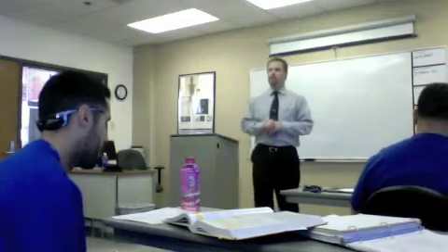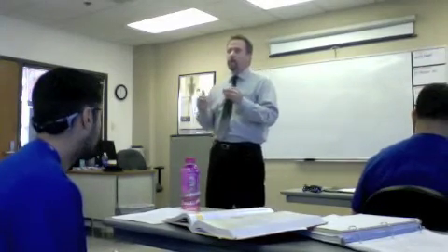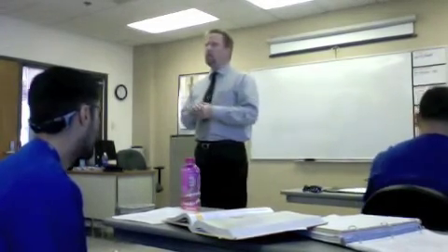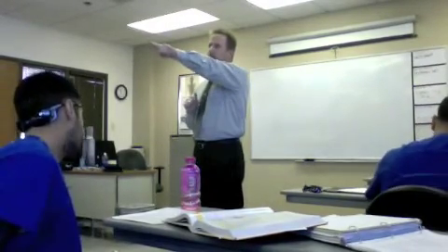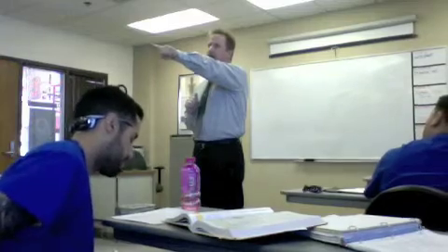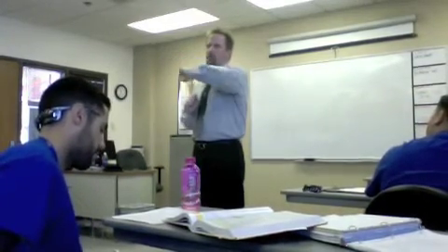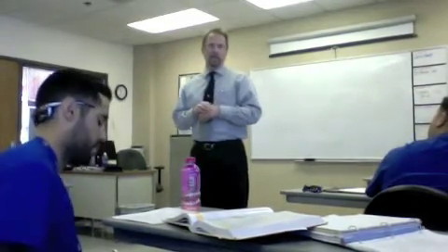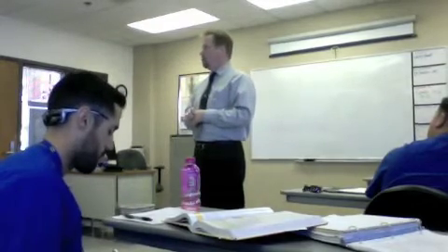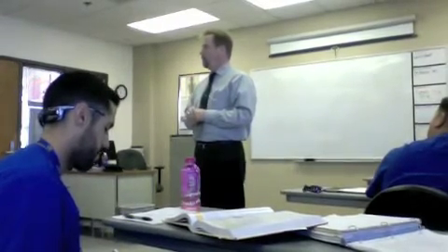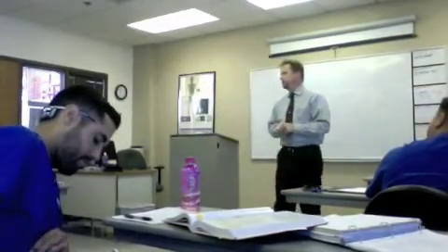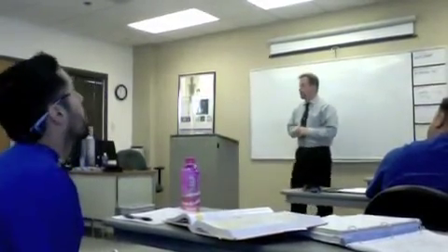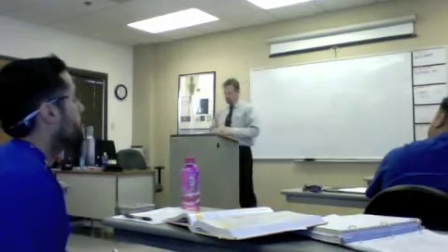When you have a dedicated chest room, most Bucky grids are 12 to 1, or 16 to 1. It is so critical that you're centered to the center of it and perpendicular to it. The only application of a 16 to 1 grid ratio would be in a dedicated chest room or something. Otherwise, you would have grid cutoff. The majority of Buckys are 12 to 1.